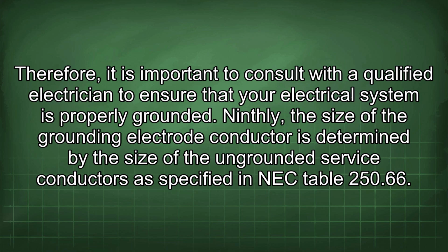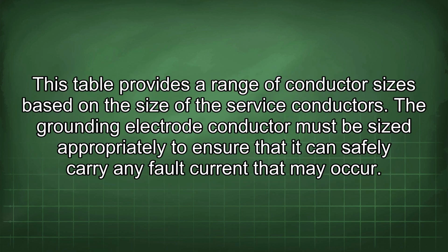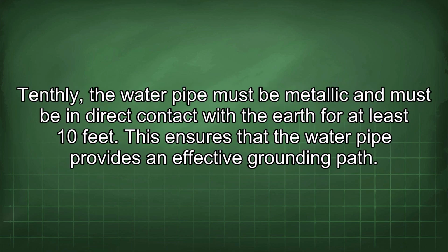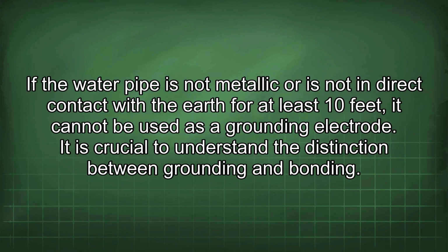Ninthly, the size of the grounding electrode conductor is determined by the size of the ungrounded service conductors as specified in NEC Table 250.66. This table provides a range of conductor sizes based on the size of the service conductors. The grounding electrode conductor must be sized appropriately to ensure that it can safely carry any fault current that may occur. Tenthly, the water pipe must be metallic and must be in direct contact with the earth for at least 10 feet. This ensures that the water pipe provides an effective grounding path. If the water pipe is not metallic or is not in direct contact with the earth for at least 10 feet, it cannot be used as a grounding electrode.